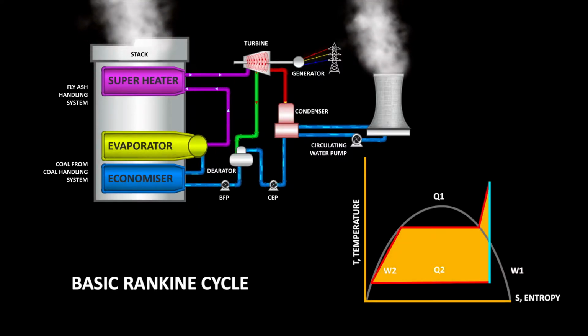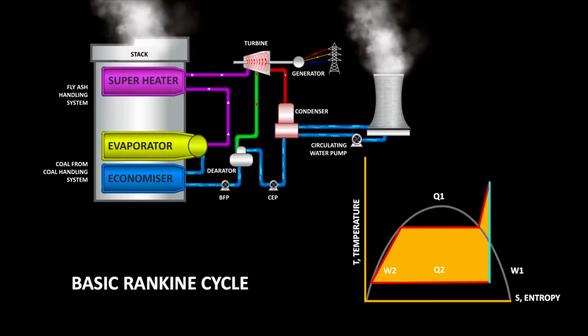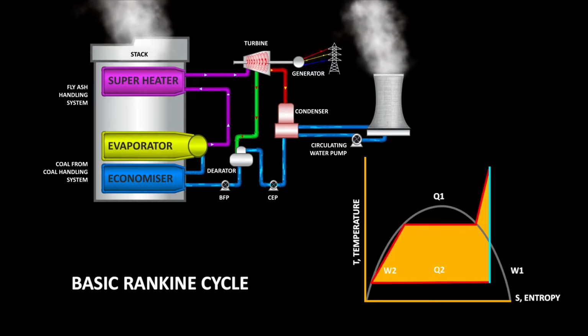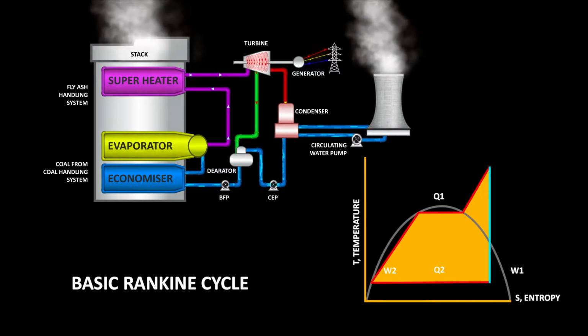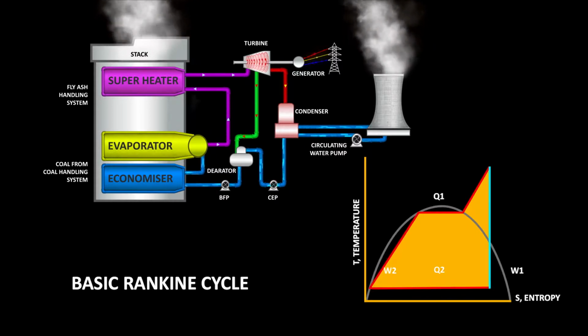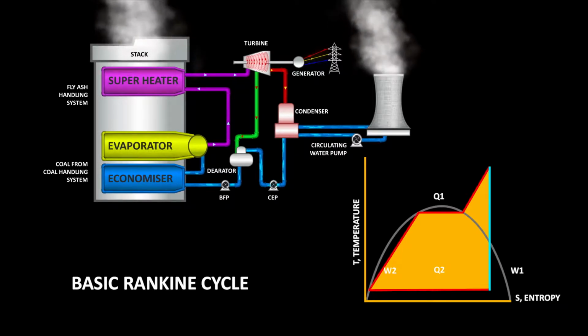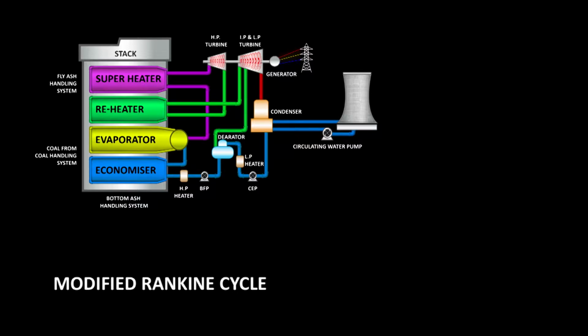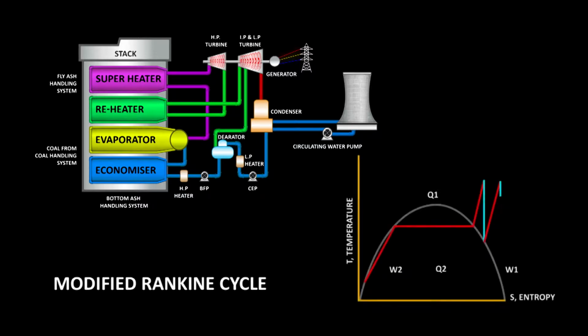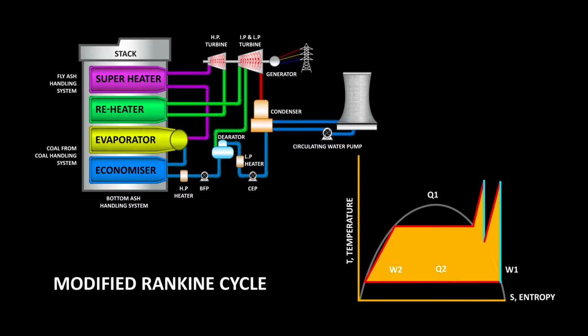The basic Rankine cycle efficiency can be improved further in these ways: increasing the superheater steam temperature, increasing the superheater steam pressure, and increasing the condenser vacuum. However, in modern power plants, a modified Rankine cycle is followed for better cycle efficiency. 2 more processes are incorporated in the basic Rankine cycle to improve cycle efficiency. They are reheating and regenerative feed water heating.